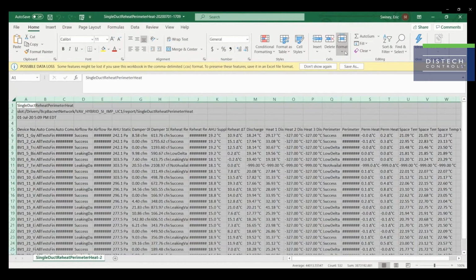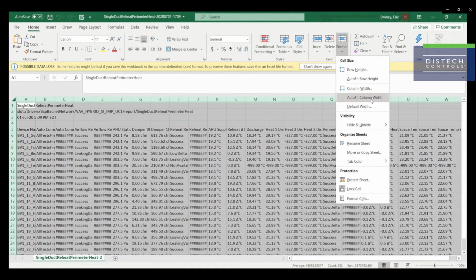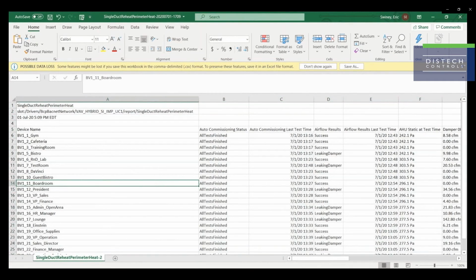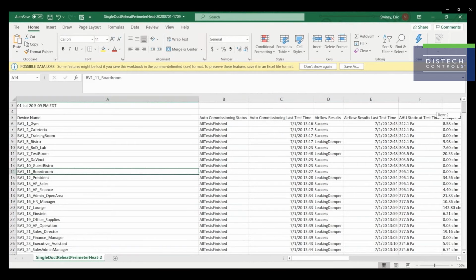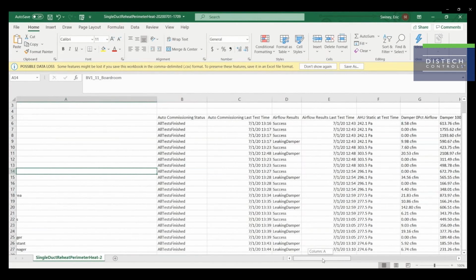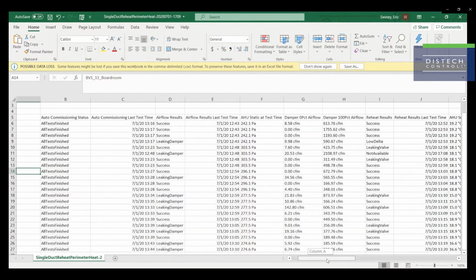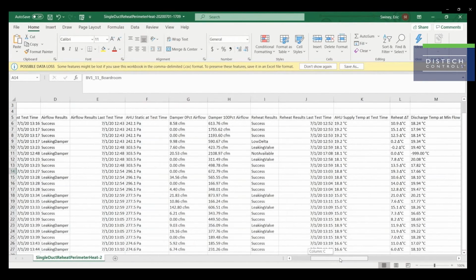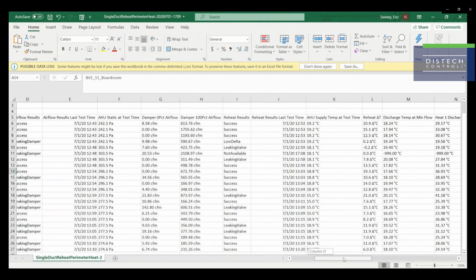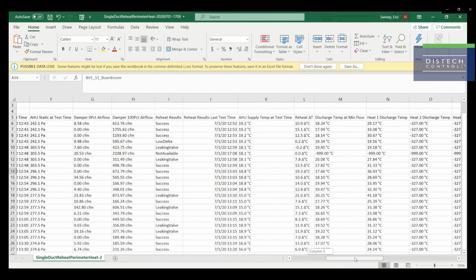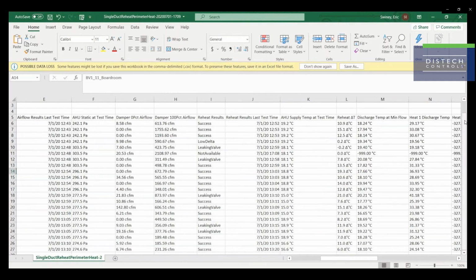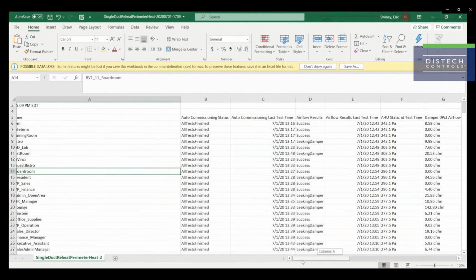I'm going to quickly adjust the column width so we can take a better look at this report. We can see here our test results and our test times. We can see what measured data is and our latched AHU value. You can see many results here: success, low delta, leaking valve, and not available. If you see not available, this means that there's either no read or that there was not a discharge air temperature sensor installed for this test.